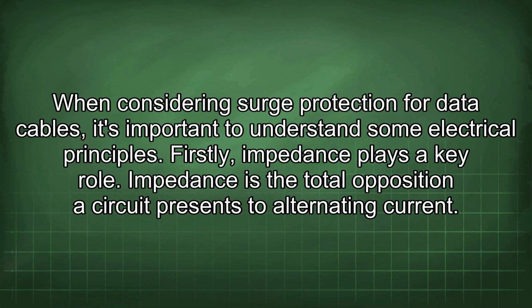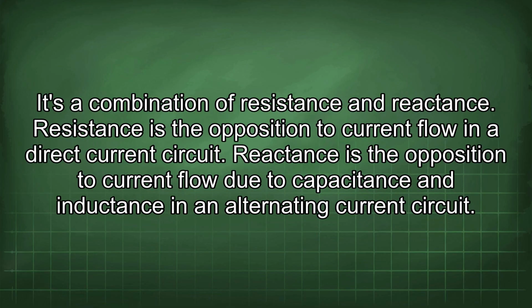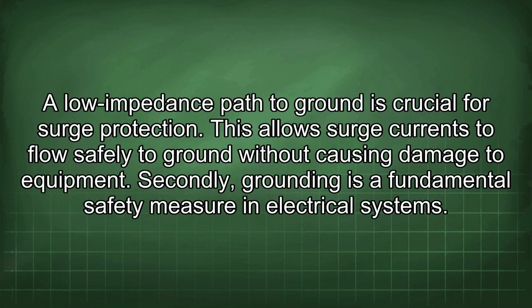When considering surge protection for data cables, it's important to understand some electrical principles. Firstly, impedance plays a key role. Impedance is the total opposition a circuit presents to alternating current. It's a combination of resistance and reactance. Resistance is the opposition to current flow in a direct current circuit. Reactance is the opposition to current flow due to capacitance and inductance in an alternating current circuit. A low impedance path to ground is crucial for surge protection. This allows surge currents to flow safely to ground without causing damage to equipment.